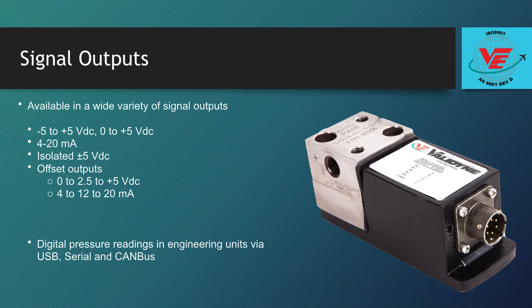The P365 is also available with the most commonly specified output signals. The standard output is 0 to plus or minus 5 VDC over the plus or minus full-scale pressure range. This can be offset so that the minus full-scale pressure is indicated by 0 volts DC, 0 pressure by plus 2.5 volts DC, and plus full-scale pressure by plus 5 volts DC.